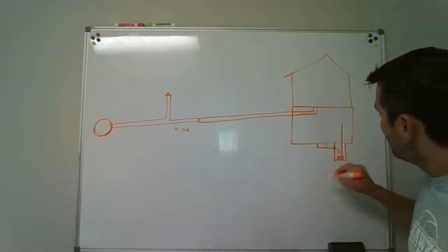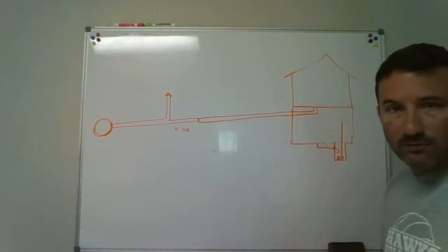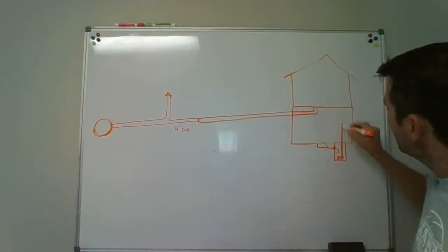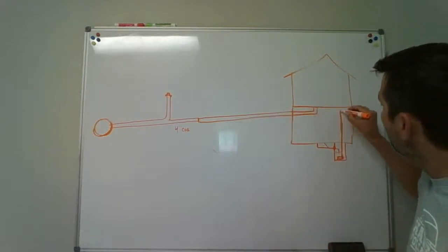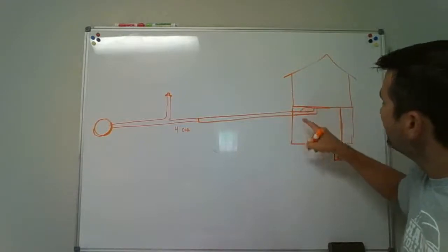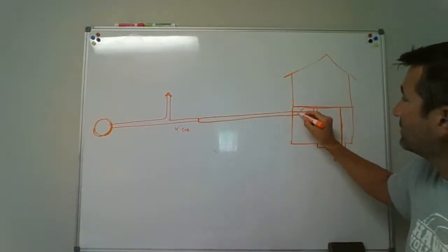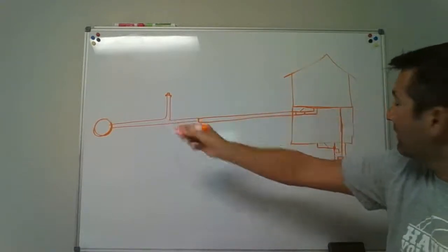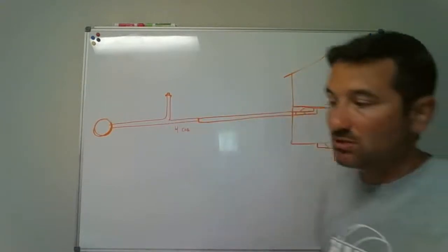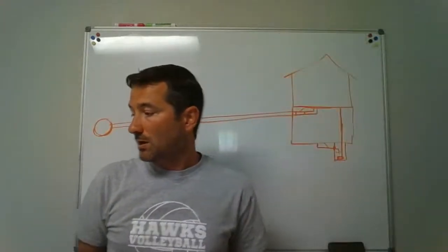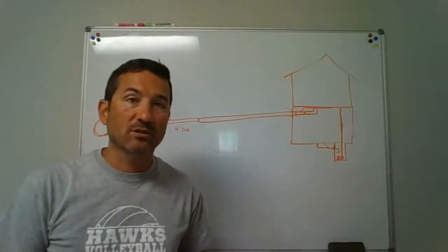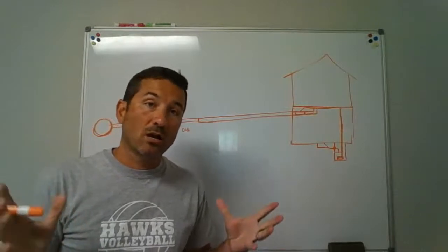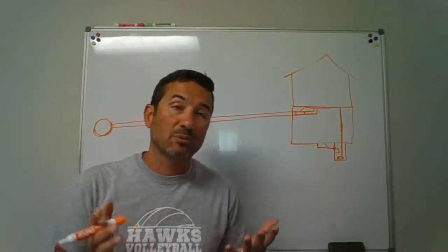And it will grind everything, the toilet paper, everything else that's in there, grind it up, shoot it out up here, and we pump it up, and it comes across and then ties in through a Y connection back into the existing line to where now it's going to flow by gravity out. But we're going to pump that out. So that's what this sewage ejector is. If it's just clear liquid waste, you could do some type of sump pump.